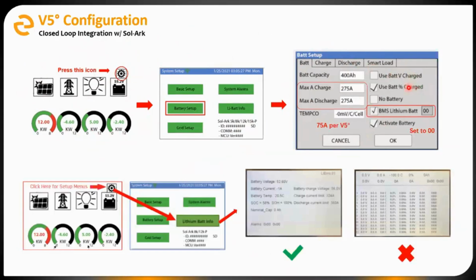You're going to want to check the use BAT percent charged, activate battery, and BMS lithium BAT. You need to make sure that this BMS lithium BAT is set to 00. That basically tells the Sol-Ark now it's looking for a Pytes battery. Over here, we'll set these to 75 amps per V5. So it sort of depends on your installation, how many batteries are there. Once this is all entered, hit OK to save.